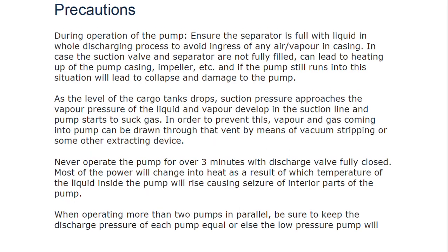During operation, ensure the separator is full with liquid throughout the entire discharging process. Any ingress of air or vapor in the casing can lead to heating of the pump casing. If the pump runs in this situation it will lead to collapse and damage to the pump. As the level of the cargo tank drops, suction pressure approaches the vapor pressure of the liquid and vapor develops in the suction line. To prevent gas coming into the pump, it can be drawn through the vent by means of a vacuum stripping pump. Never operate the pump for more than three minutes with the discharge valve fully closed — most of the power will convert into heat, raising the temperature of the liquid inside the pump and causing seizure of interior parts.